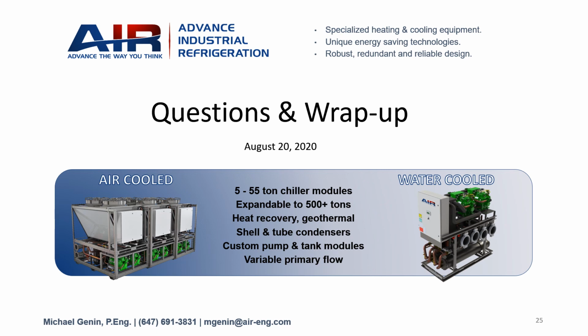How much lift can the heat recovery chiller provide? So this means what's the hottest temperature versus the coldest temperature in the evaporator on the cooling side. This is heavily dependent on the compressor technology to use, but it's not certainly out of the realm that a heat recovery chiller can provide, let's say 10 or 15 Fahrenheit chilled fluid and 160 degree heat recovery. It will vary from manufacturer to manufacturer. It will be a function of what refrigerant they're using, and it will also be a function of the compressor type they're using.